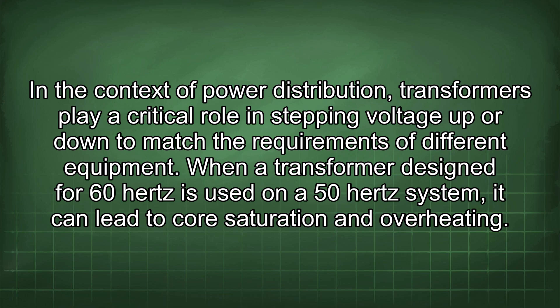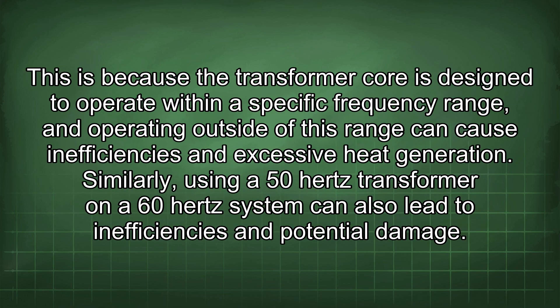In the context of power distribution, transformers play a critical role in stepping voltage up or down to match the requirements of different equipment. When a transformer designed for 60Hz is used on a 50Hz system, it can lead to core saturation and overheating, because the transformer core is designed to operate within a specific frequency range. Similarly, using a 50Hz transformer on a 60Hz system can also lead to inefficiencies and potential damage.